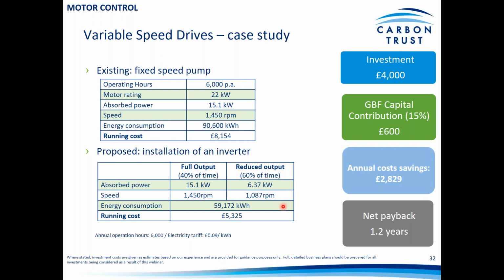So a saving there of about 30,000 kilowatt hours, which works out in cost terms to be a saving of about £2,800 a year. So that was achievable for this motor size for an investment of £4,000, and it's often the case that you can install variable speed drives on existing motors. You don't necessarily need to replace them. The inverter or the variable speed drive can be installed with an existing motor to vary the frequency and to vary the speed of the existing motor. In this case, we were able to give a capital contribution of 15%, around £600, and overall that led to a net payback of just 1.2 years, and you can see that's a very attractive return on investment.